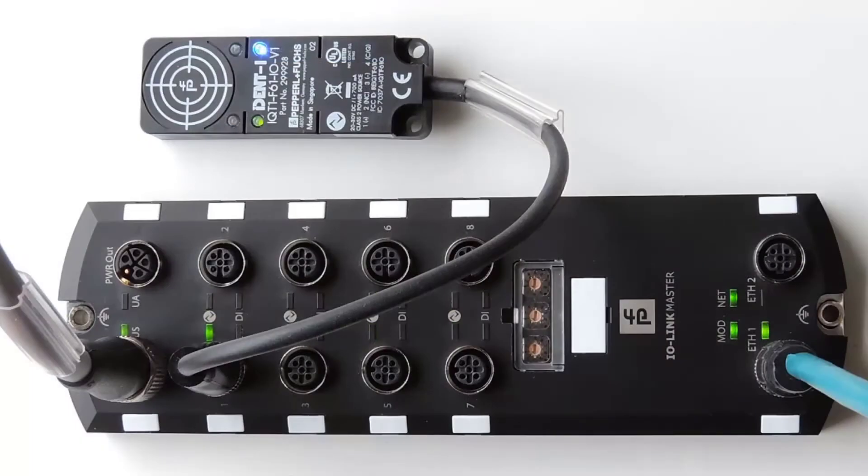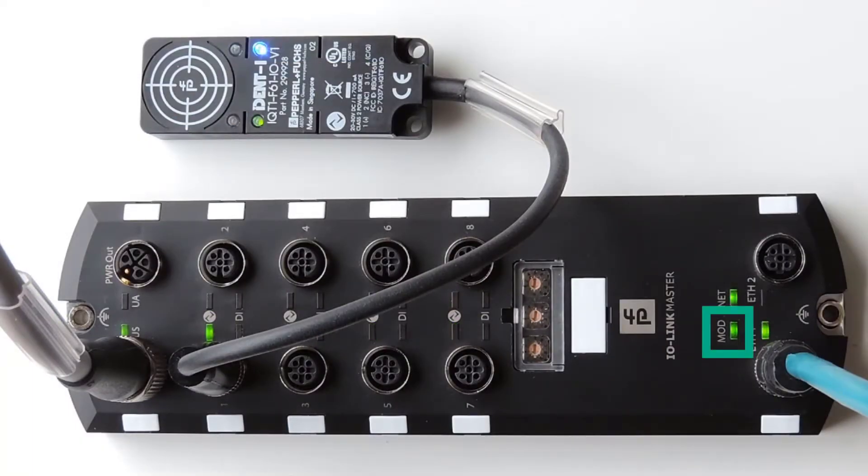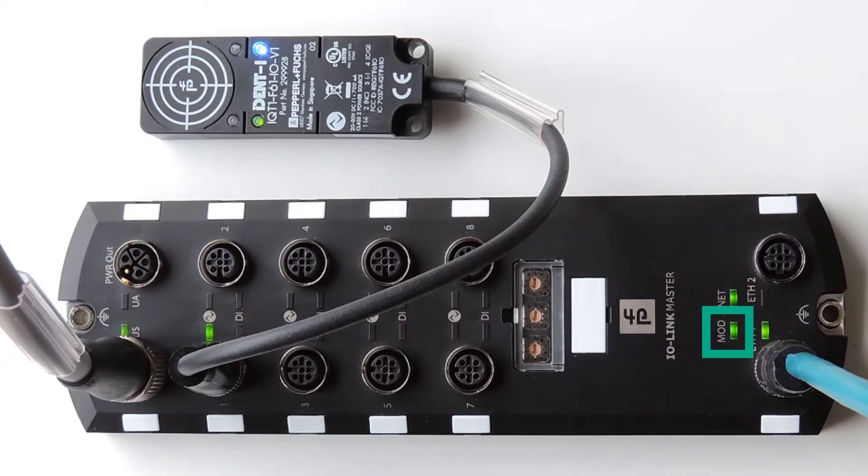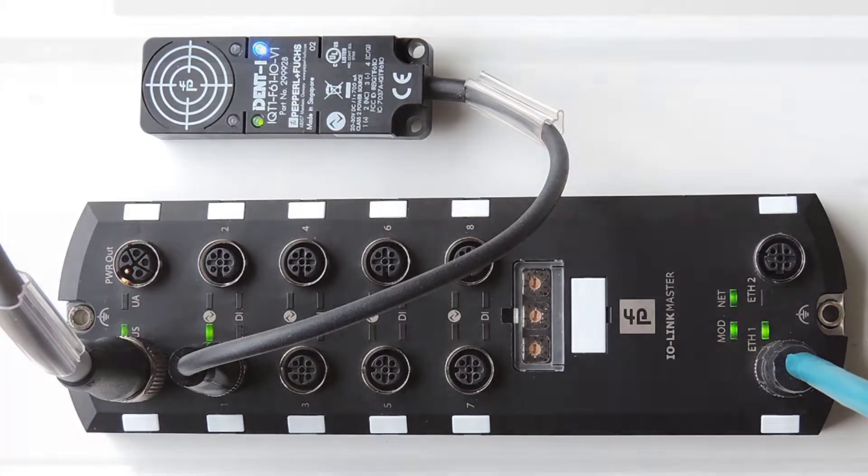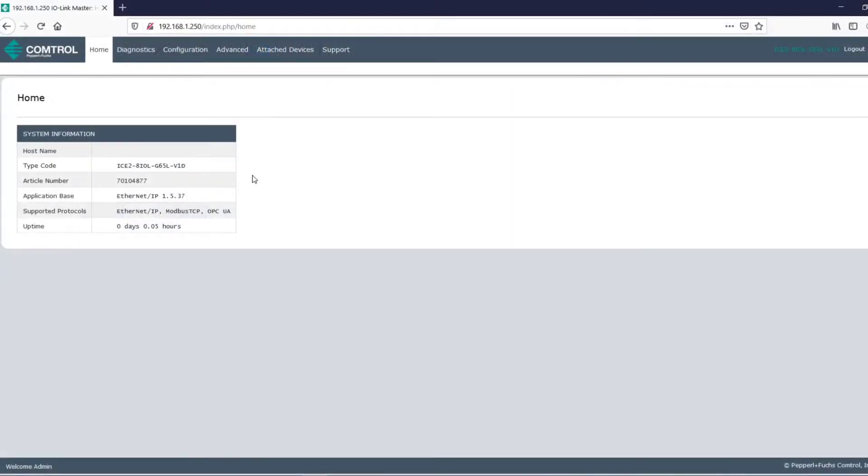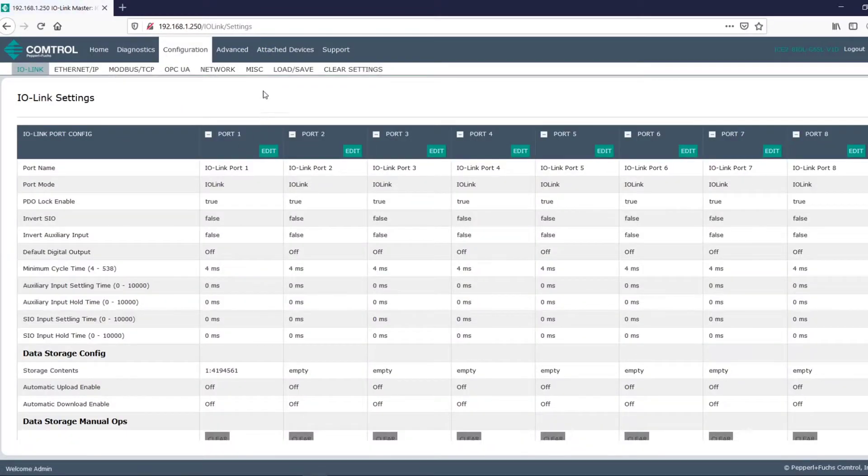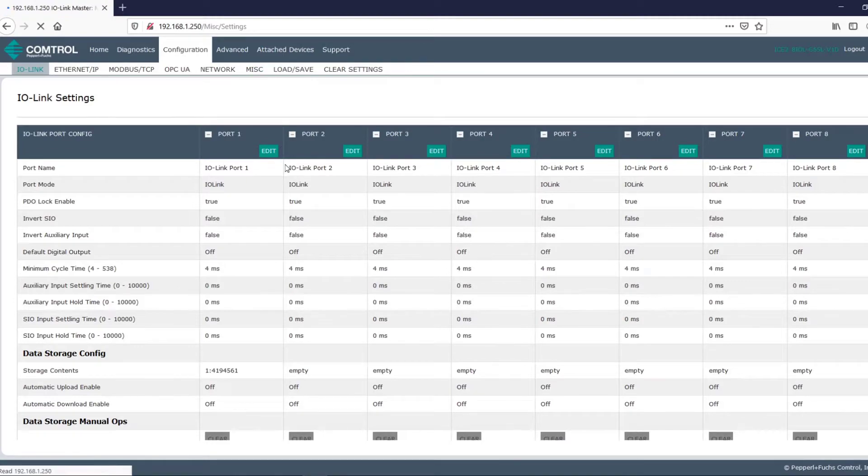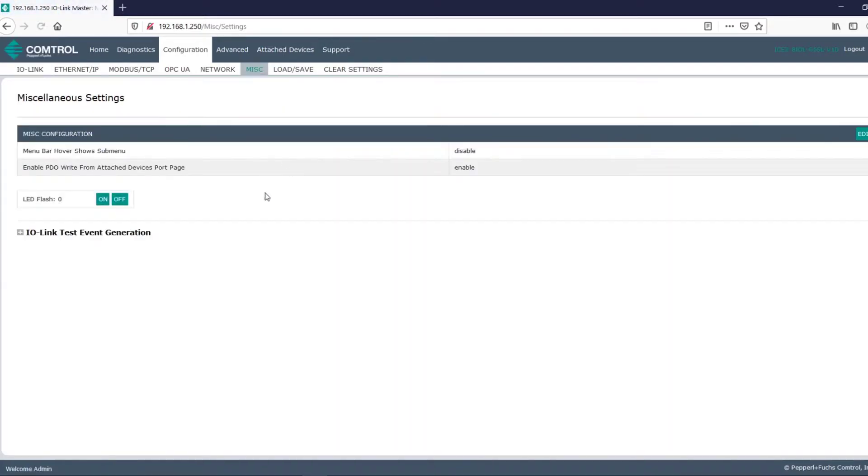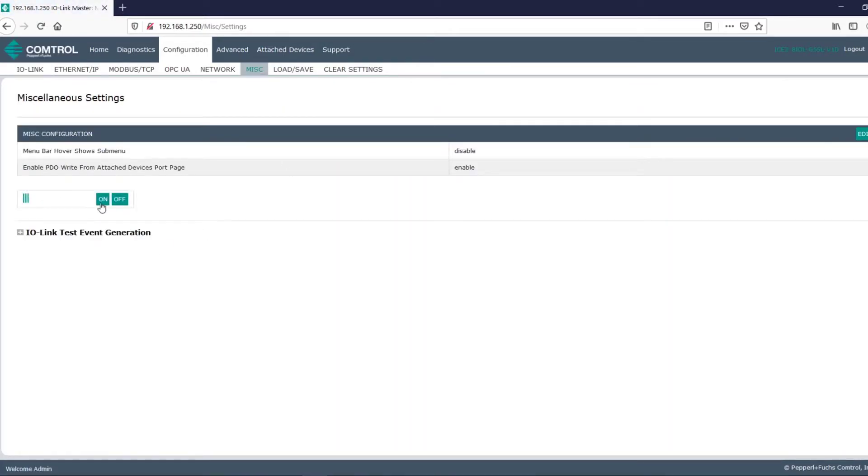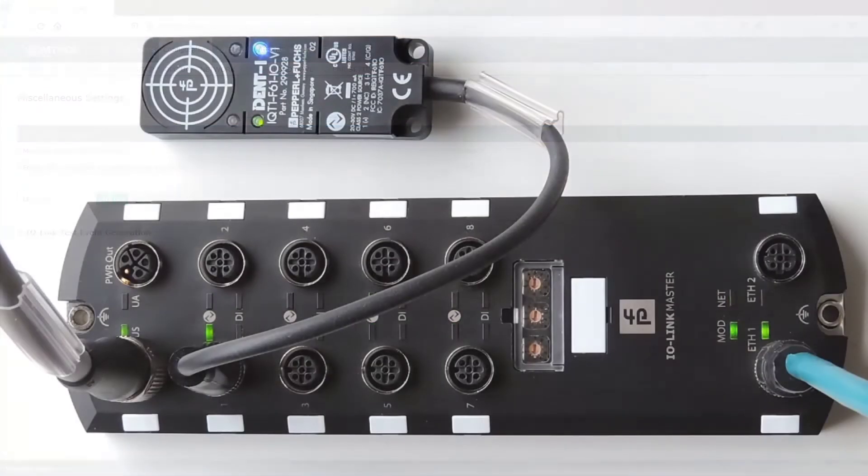Alright, let's check out our IO-Link master. If the mod LED is solid green, the IO-Link master is ready for operation. And, if we want to further prove that we're communicating with our IO-Link master, let's go ahead over to the configuration tab, click on miscellaneous, and then turn LED flash to on. If we did everything right, our ICE 2 block will light up nicely.